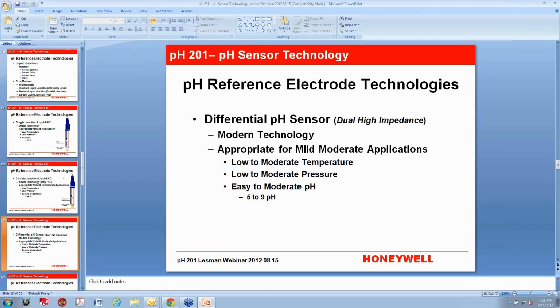So dual high impedance refers to having two high impedance sensors: the pH measuring electrode that measures the process, and a pH measuring electrode that's sitting in a buffer. The idea is that as the process starts to poison the potassium chloride and moves into the area, number one, it gets diluted by the potassium chloride, and then as it moves into the area where the second pH sensor is, it's moving into a buffer solution, which of course is designed to hold its pH, and so that slows down the attack on the reference.